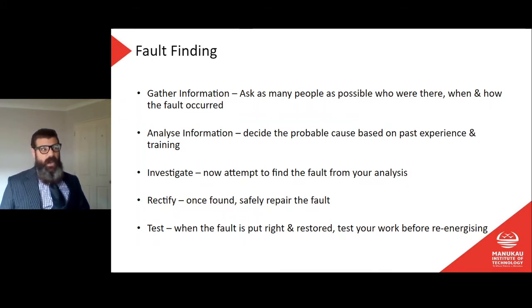I used to interrogate people, especially if it was something that was really intermittent. Like they said, oh, this happened last night, but now it's working again. Or this has happened 3 times in the last week, but then we just turn the pump off and on again and it works. So when you get there, the fault might not actually be there.